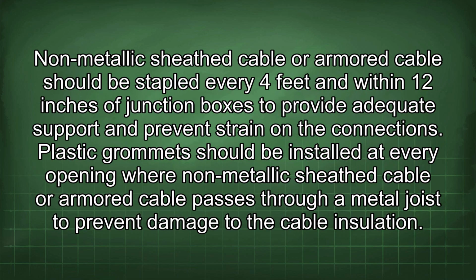Non-metallic sheathed cable or armored cable should be stapled every 4 feet and within 12 inches of junction boxes to provide adequate support and prevent strain on the connections. Plastic grommets should be installed at every opening where non-metallic sheathed cable or armored cable passes through a metal joist to prevent damage to the cable insulation.